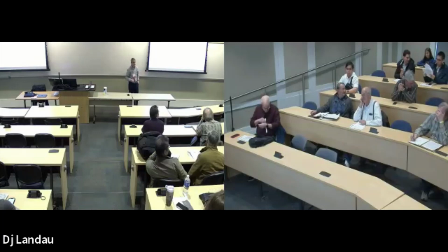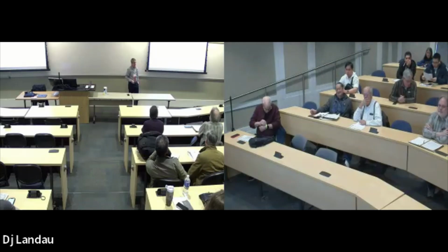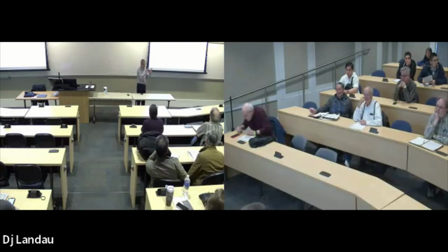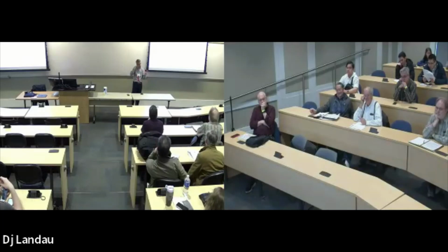Yes, question. Would I be correct then to assume that a brownout is what happens when you've lost one but still have a little bit, or is that while one substation is ramping up? What exactly is a brownout? That's the question. Okay, so there's a brownout and there's a blackout. Neither are good. The blackout's worse. I mean, there's no service. A brownout is typically what happens when you don't have sufficient generating capacity to serve all the demand. It's a really hot day. You've got some generating units that are out and you can't quite meet the demand on the system. Almost, but not quite. So you don't want to shed load. In other words, you don't want to black out customers and bring that balance back between generation supply and the demand. What you do is you lower the voltage on the network, usually on the distribution network. That's why it's called a brownout. You probably can't tell that it's happening, but the voltage is a little lower. That brings the demand down enough to ride through that peak period. So that's the difference between brownouts and blackouts.